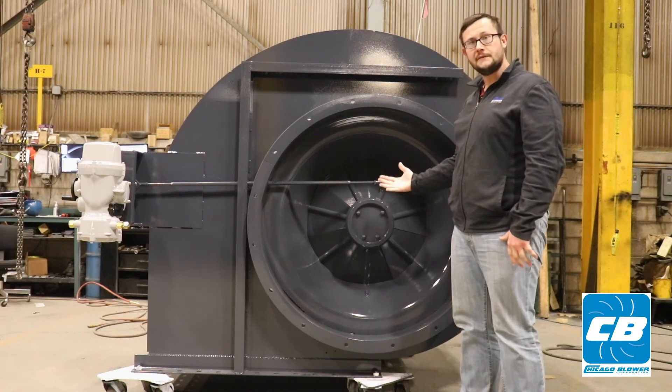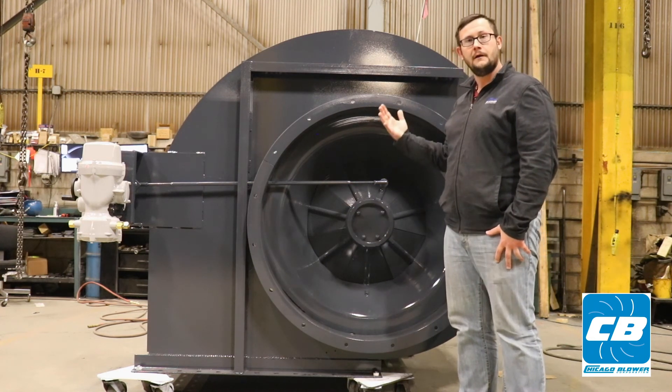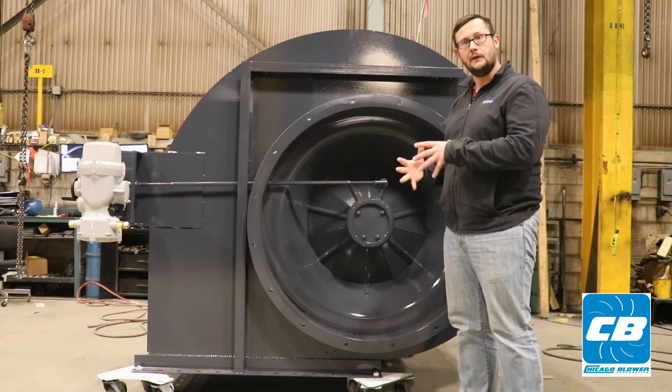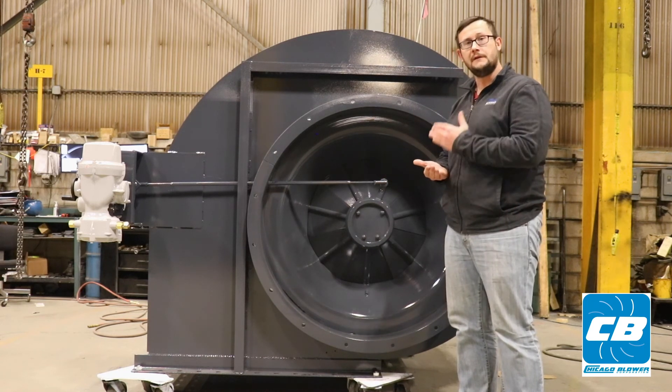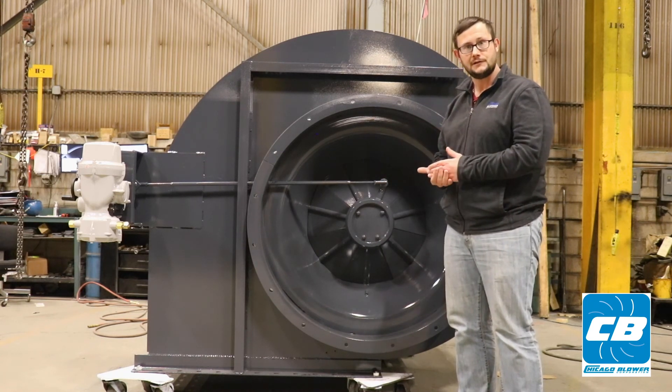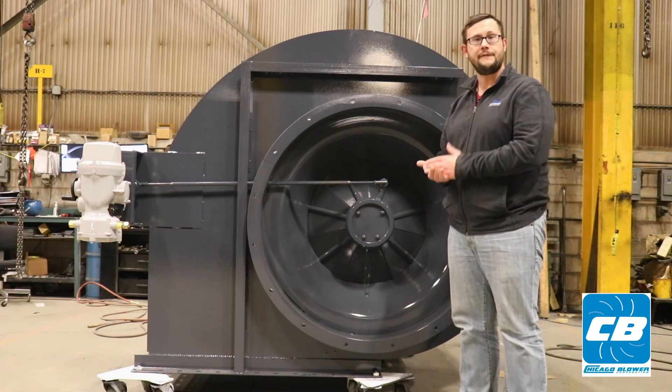The convenience of the PFD fan is it's available in an Arrangement 4 configuration, which means the wheel is mounted directly onto your motor shaft. There's no need for bearings, no need for coupling, no need for lubrication. As long as the motor runs, the fan runs — which is typically very reliable and stress-free.